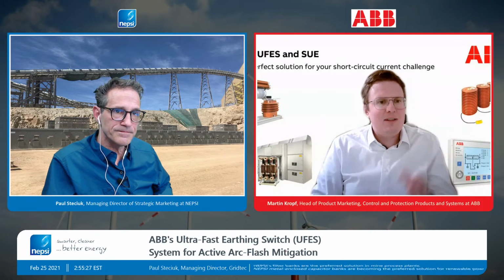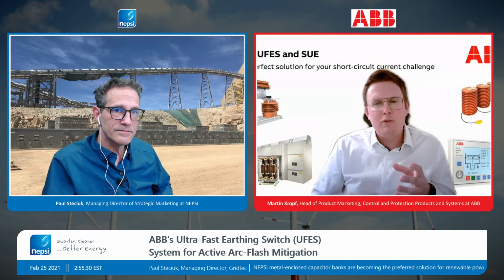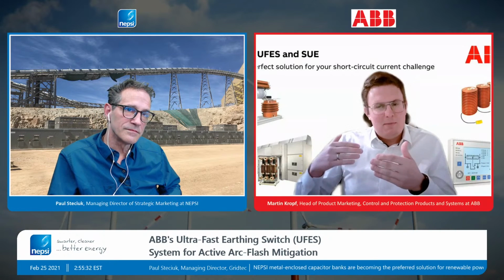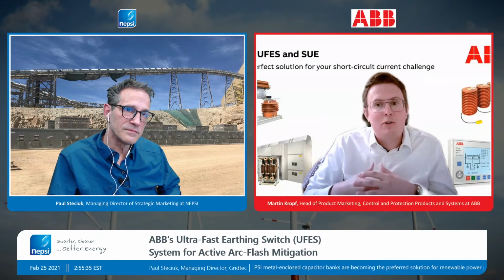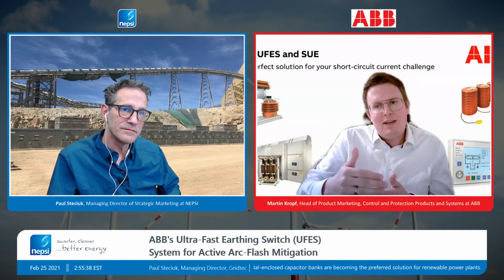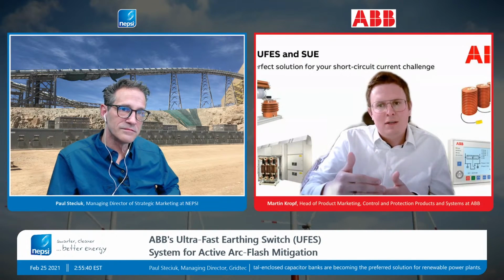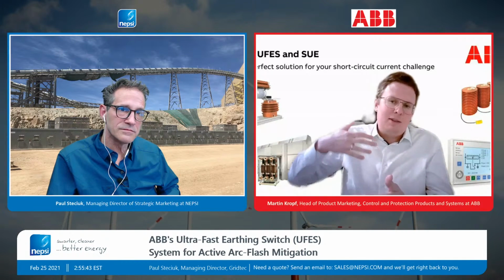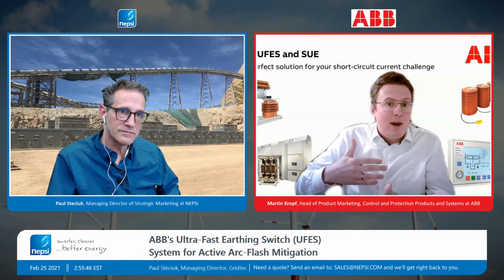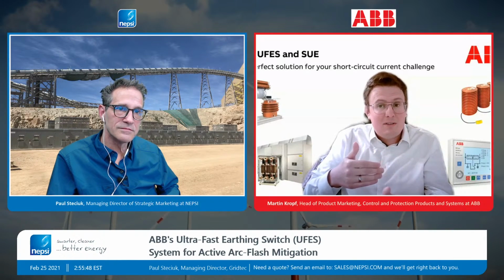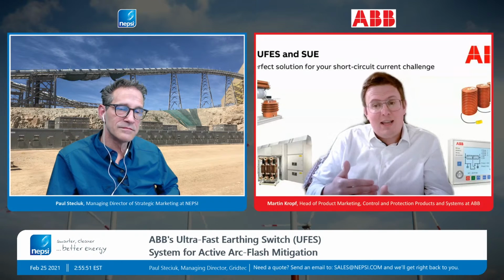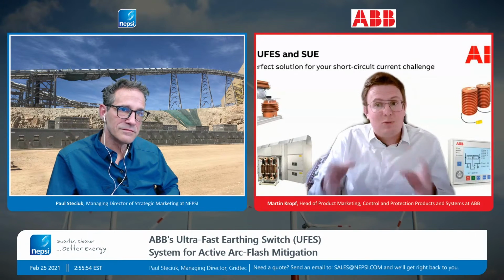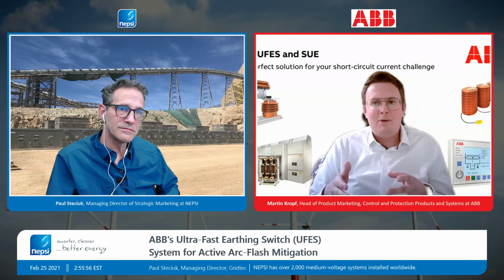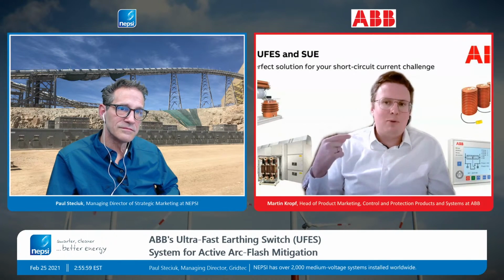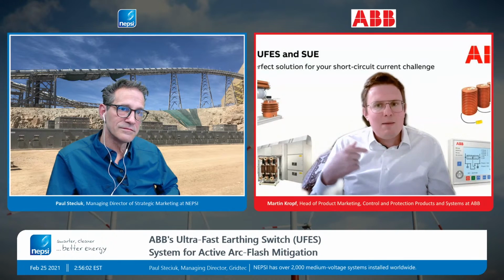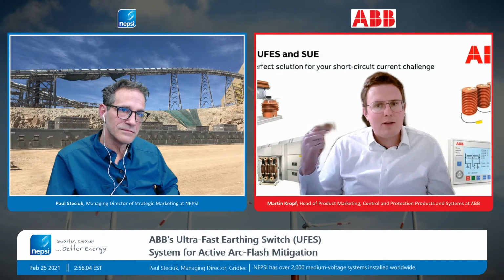Let's assume we have seen it in your application, in your big gear. You have the UFES really in the entry, where I guess the cable comes in with all the energy, and then you have your capacitor bank. So you really have it at the beginning. So the question is, what do you have prior to the UFES, looking at where the energy comes in? Is there a breaker in your gear, or is there just a cable coming? And if a cable is coming, you have to ask yourself, if you design the switchboard with the customer, what happens if UFES is tripping? Is there on the other side a breaker? Is this breaker my breaker, or is this a utility breaker?